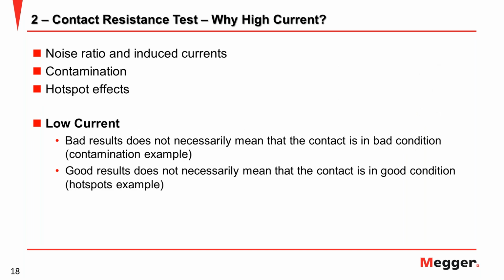The reason why high current is needed for testing the circuit breaker, there are some reasons. The first is noise ratio and induced current. The second one is contamination, and the last one is hotspot effect. These three components can be eliminated when you use high current. For detailed information about this, you can see my webinar about the practical contact resistance test. There is a more detailed explanation there, but in general, these three parts can affect the contact resistance measurement, and to eliminate these three components, you need to use high current. Okay, this is the reason.